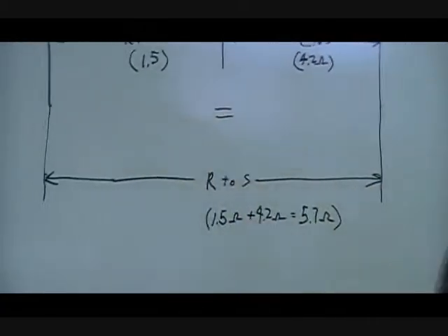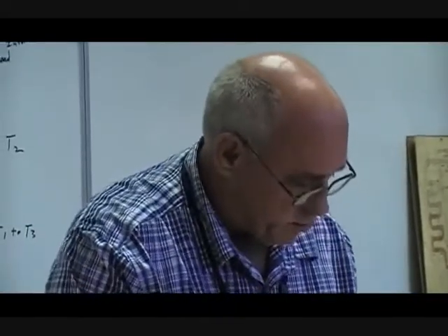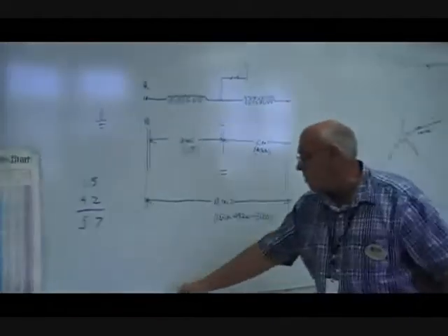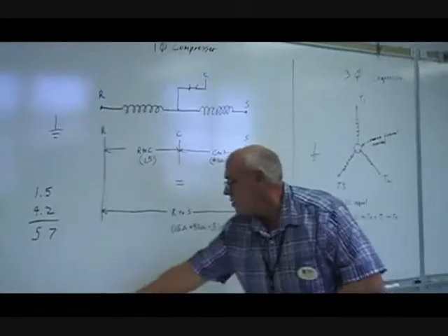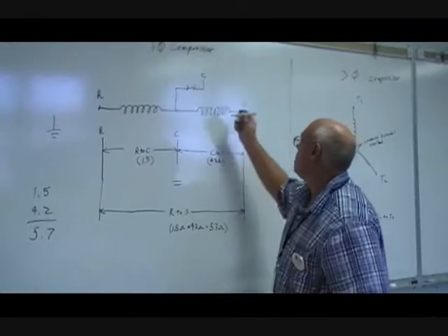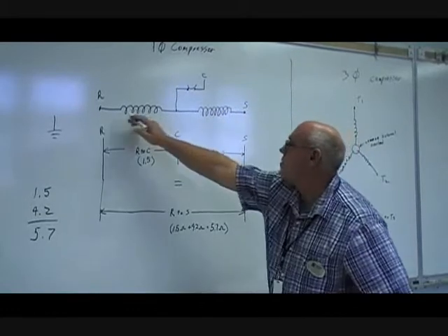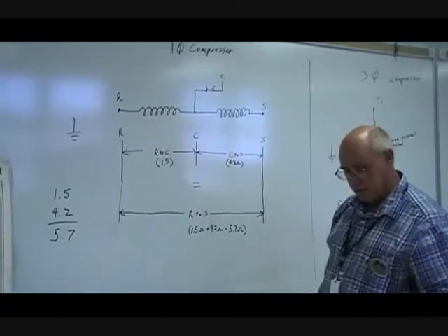There's many different failures that can happen between that. Some that I want to just quickly explain. If I had an open start winding, for example, I would not have the continuity between the C and the S, nor would I have it between the R and the S in that particular case.